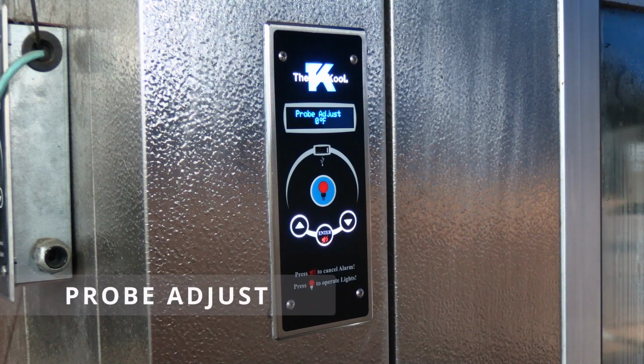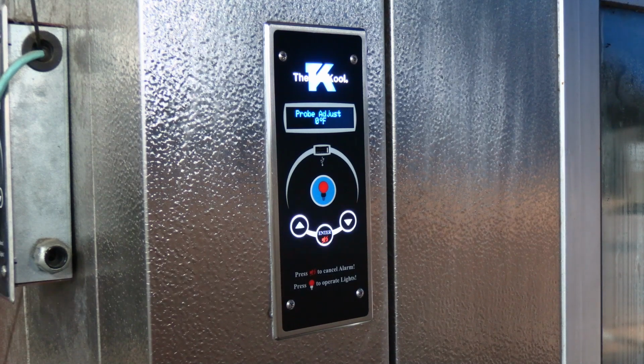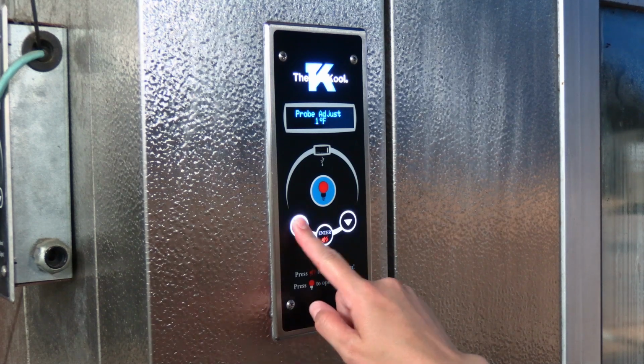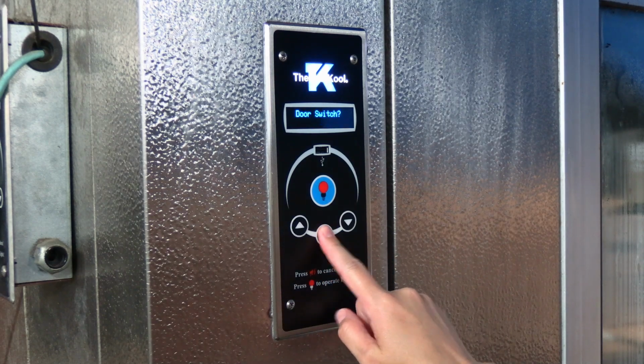Probe adjust. This option allows the temperature to be adjusted to a calibrated thermometer. This function could become necessary, given the location of the probe coupled with traffic and other operational variables that may cause a rise in temperature near the door. The default range is from -15 to 15 degrees Fahrenheit. To change the temperature, press the up or down arrow, then press enter.